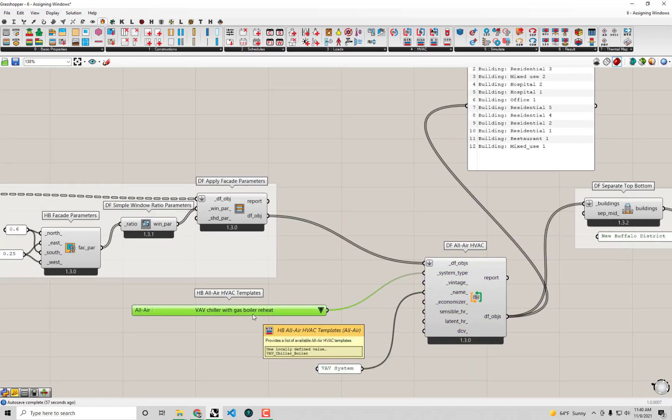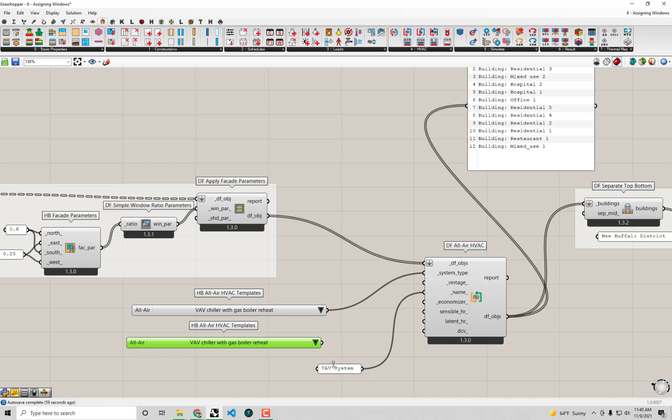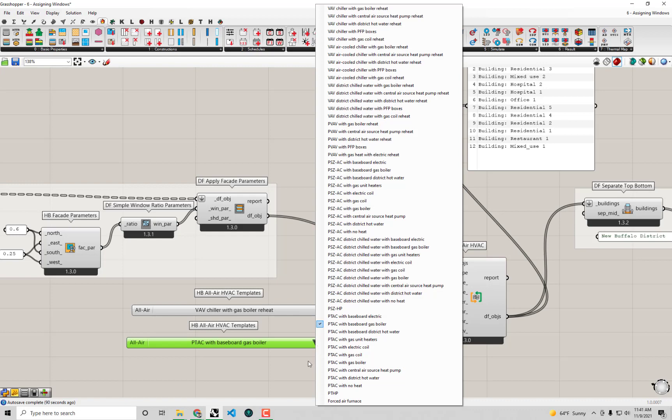So that's what I'm going to do right now. I'm actually just going to copy and paste this. So, even before I go and start editing the names here, I want to make sure that I'm using the right templates. For those of you who are familiar with the International Energy Conservation Code or ASHRAE 90.1, you probably already know that the baseline system for residential buildings is a packaged terminal air conditioner. We have a few different types of PTACs here. Keep things consistent with how we're modeling the VAV. I'm also going to use a gas boiler. In this case, we'll use gas boiler reheat. So I'm going to just select this from the drop-down of PTACs with that gas boiler reheating.